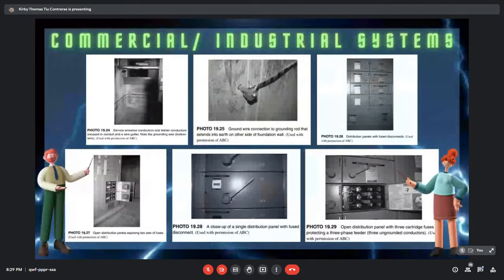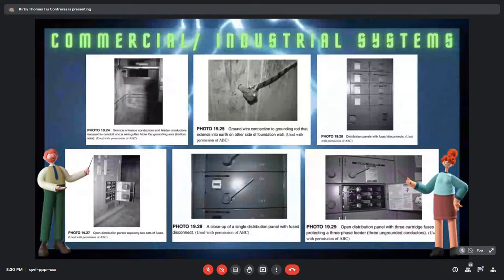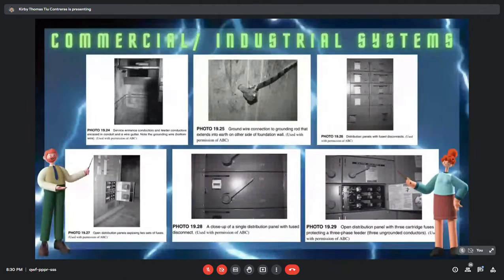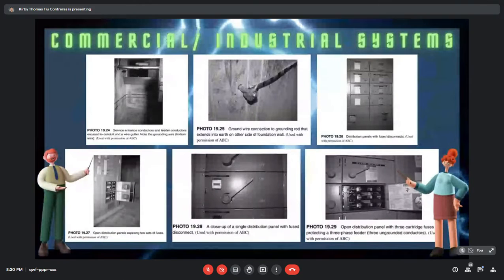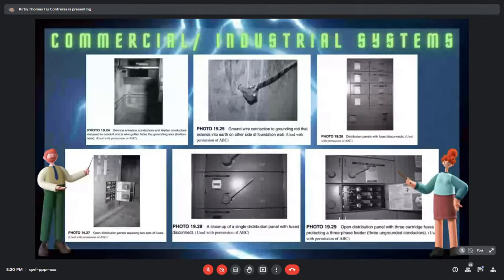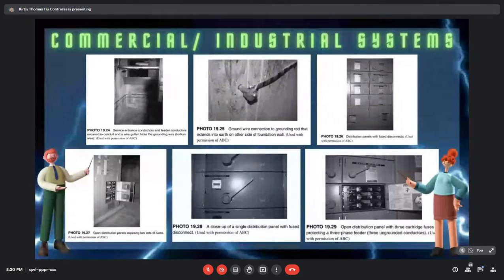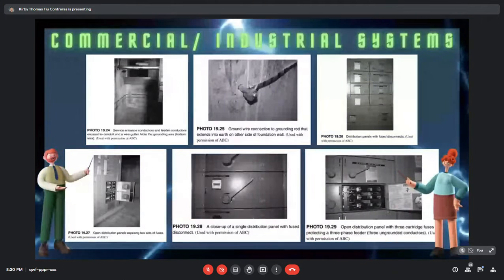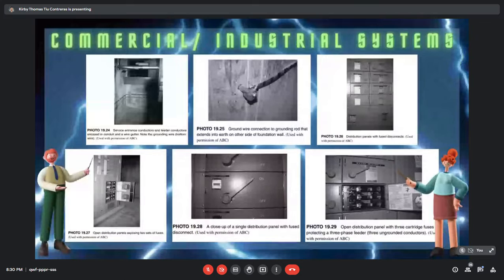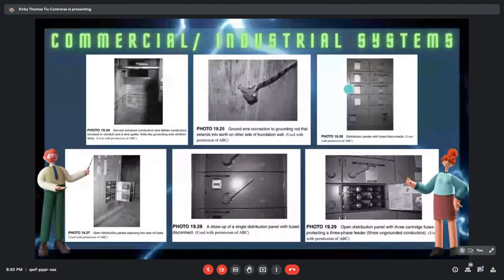Through the service entrance conductors, electrical power is transmitted to the transformer vault, and then at the step-down level the transformer distributes power to the switchboard and then to the distribution panels. The third photo shows distribution panels with fuse disconnects.